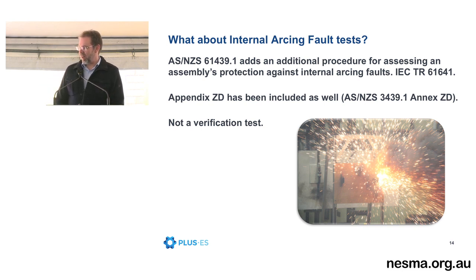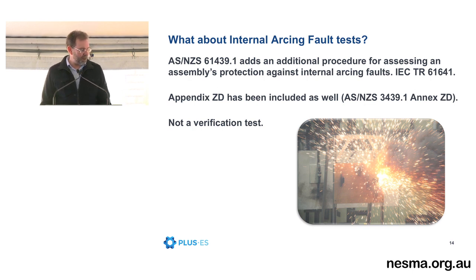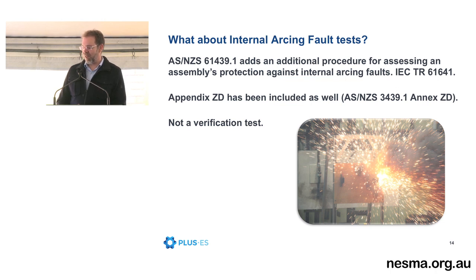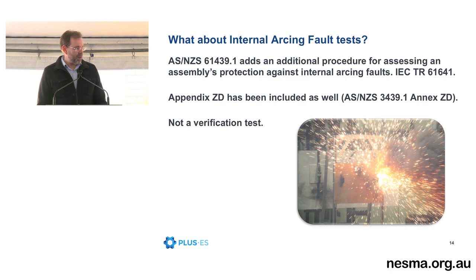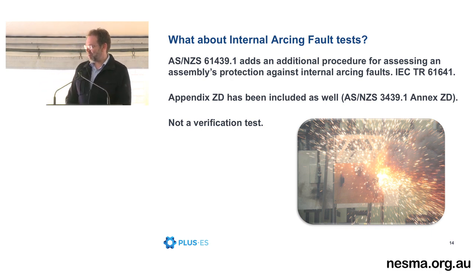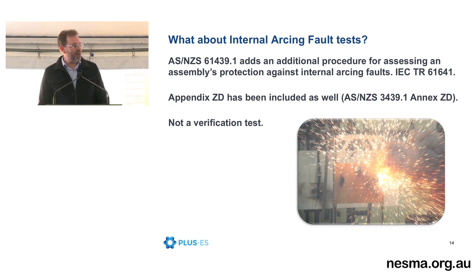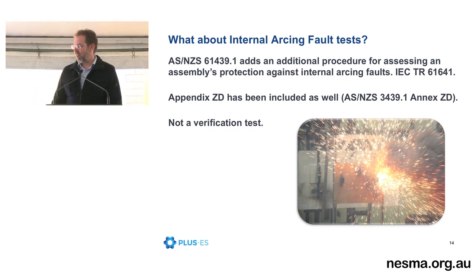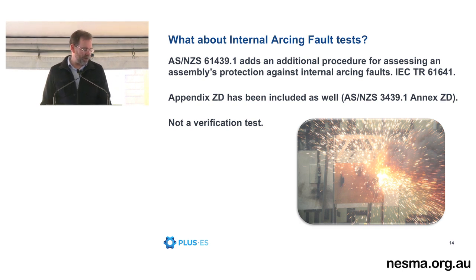The AS3439 had Annex ZD. This is probably a test that we're all familiar with. And that annex has been transported, just lifted up and dropped into the new standard. That would be another Australian variation to the overseas. That Annex ZD method, that procedure, is still in the Australian standard, which is good. However, the IEC made reference to the IEC method of doing arc fault testing, and so that is now available to the Australian standard. So there are effectively two methods now to validate arc fault performance, or internal arcing, not containment, but performance.